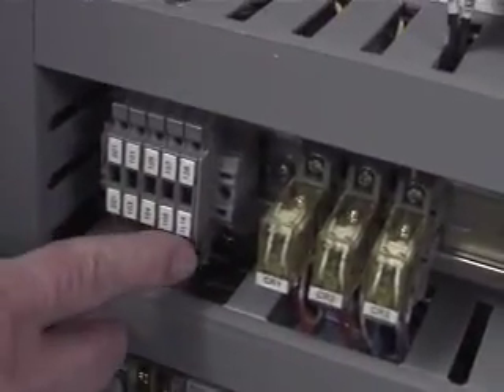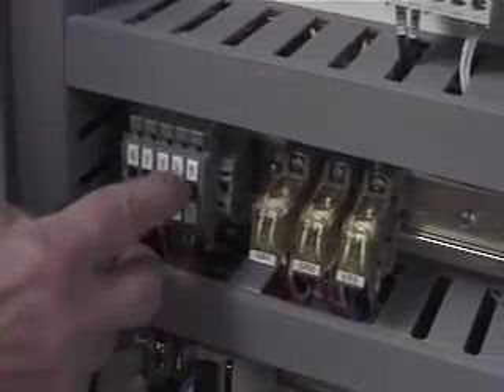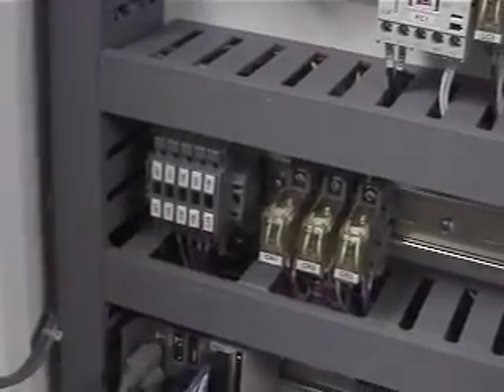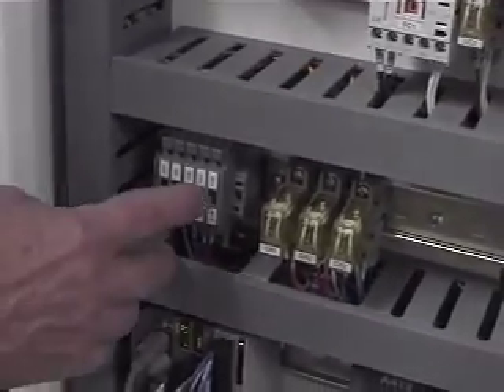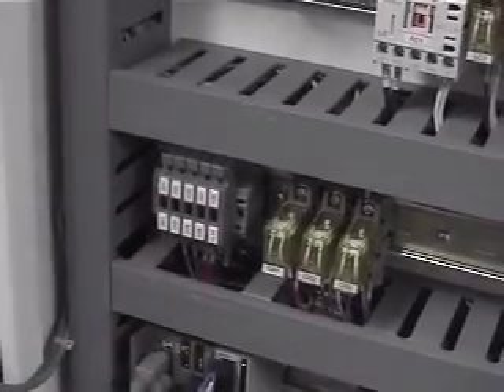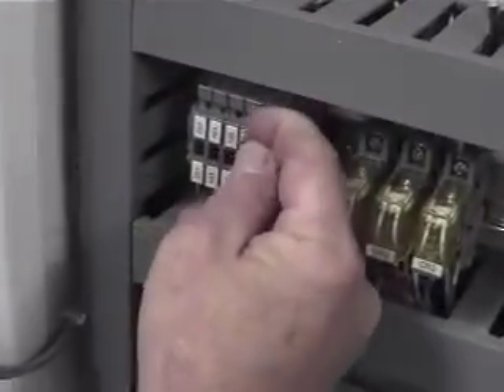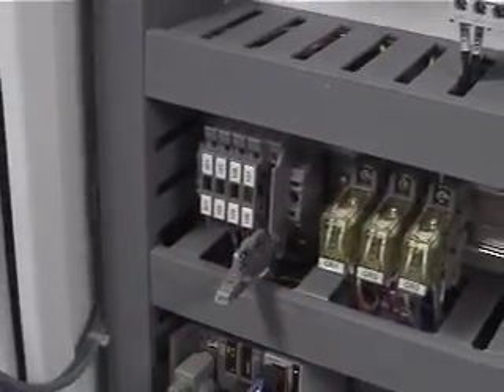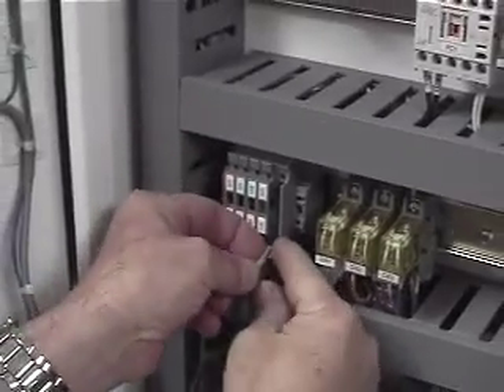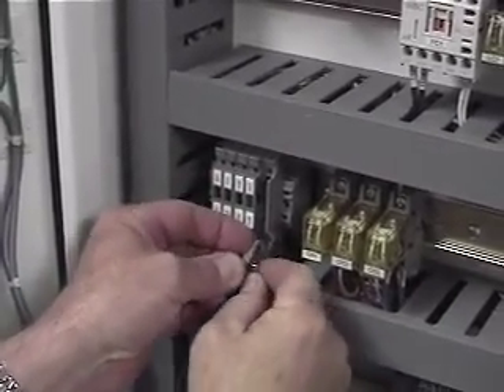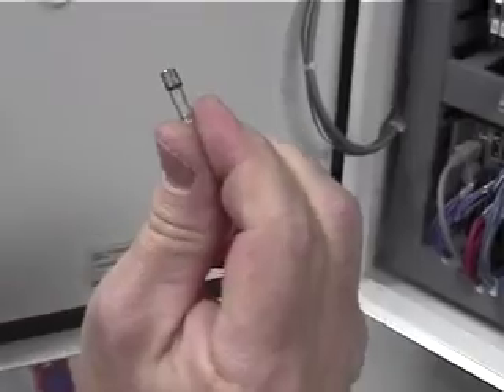So, these are fuses. The 128 is actually the door heater fuse. 107, 105, those are disconnects for your solenoids. So you literally could service a solenoid by just pulling those fuses. So if I pull that, you can see this is the fuse. It's a little GMA style fuse. Pops right out of there.